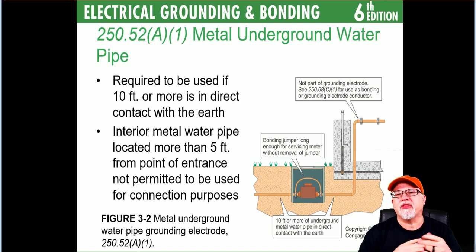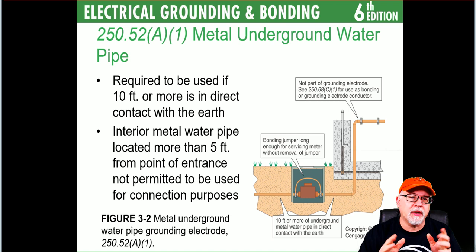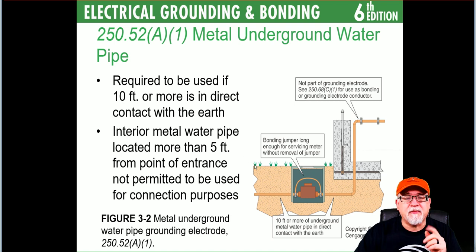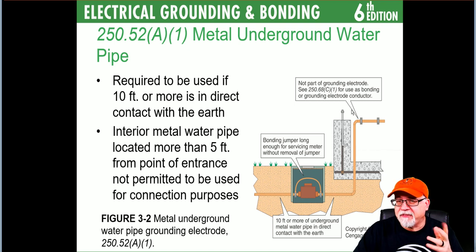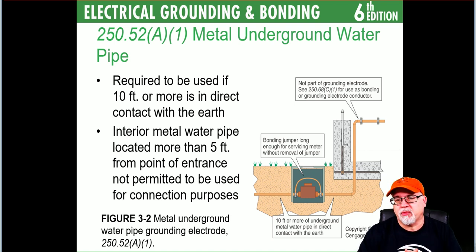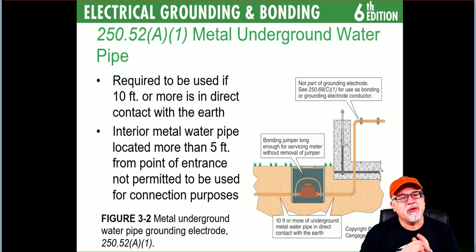250.52(A)(1) — the metal underground water pipe: required to be used if 10 feet or more in direct contact with the earth. If it's not 10 feet or more in contact with the earth, it cannot be used as an electrode. Interior metal water piping located more than five feet from the point of entry is not permitted for connection purposes — you have up to five feet to make connections to other electrodes. There is an exception in commercial applications where it's unobstructed.